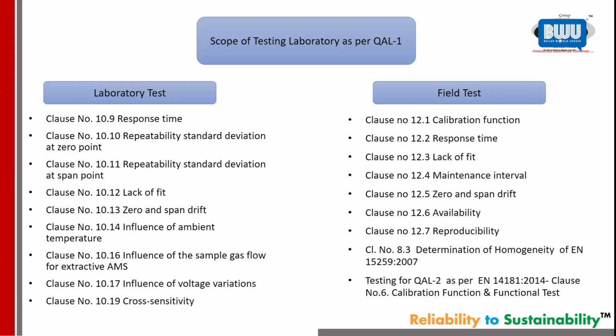So that test, you have to have 3 days, maybe 24 samples. You put them into the formula of this EN 15259, and that will give you a defined place where you should install your sampling probe to have the most homogeneous sample, for optimum result. How many of you are performing this? Nobody is performing. Everybody says we want certified.